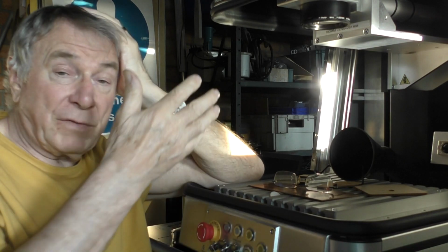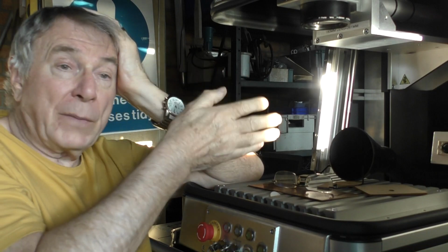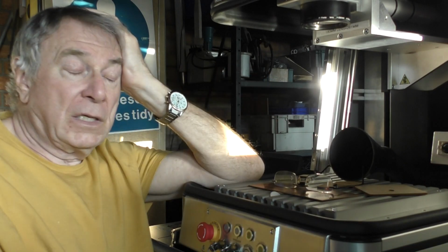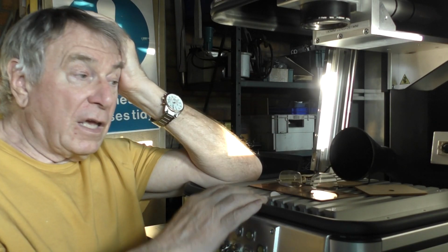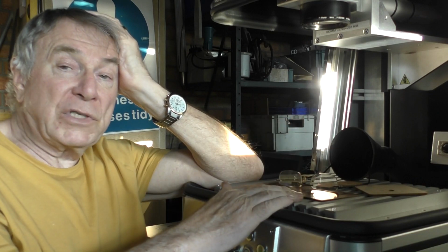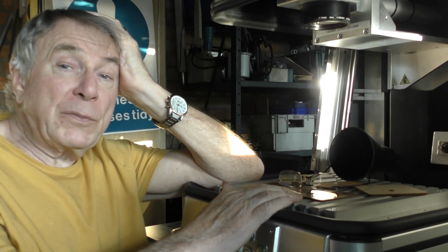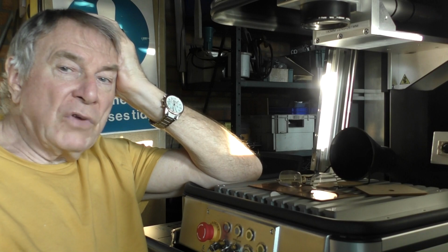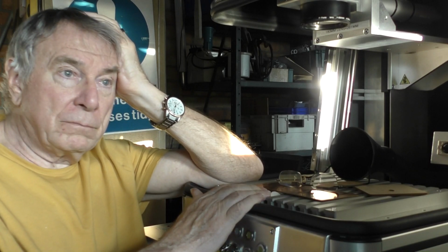But I can perceive that there is risk to the actual fibre optic interface. So the summary really is, if you stay above the focal point for your defocusing, you will never have a problem. So really the no-no is, don't focus below the focal point.